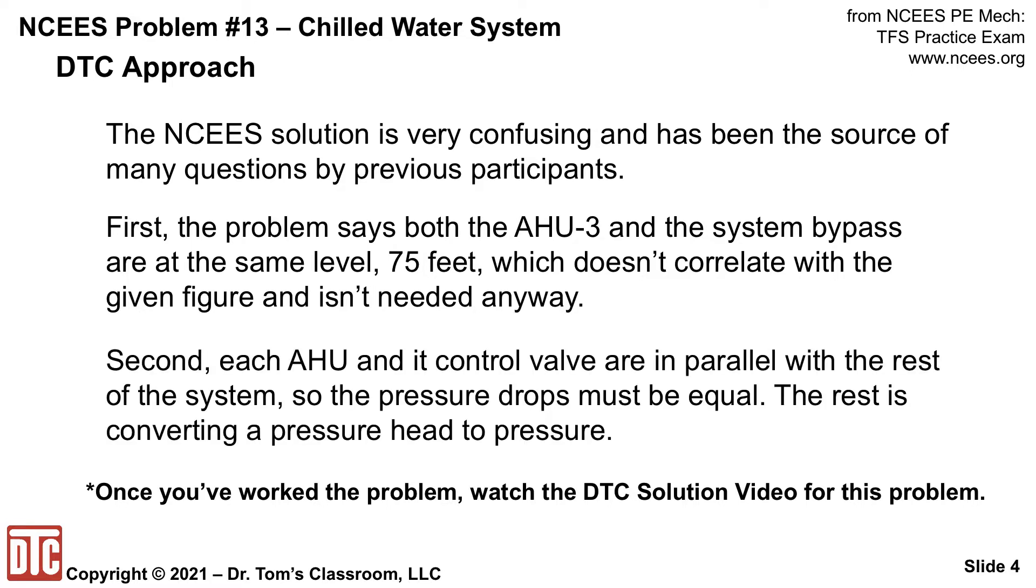And then as you see in the diagram, each air handling unit and its control valve is parallel with the rest of the system, so the pressure drops across each one of those must be equal. The rest is just converting a pressure head to a pressure.